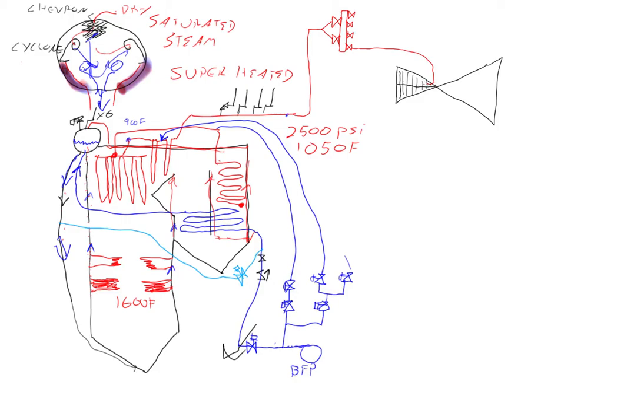So the steam flows across all of those blades and as it goes, it's got less pressure. As you take the pressure off the steam it expands, and then as it is exhausted out of the last stage here, this steam is called cold reheat.